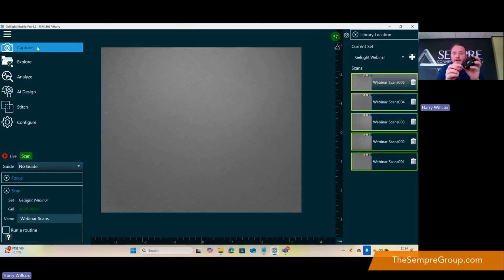Previously we would have individual artifacts, so three different artifacts within the kit. What GelSight have done this time, which is a really nice addition, is to make it so we've got this slider to walk our way through the calibration routine. So I'm now going to calibrate my 90 degree, because that was deliberately taken off the end within my process flow. I'm going to show you the principle of how we would do that.